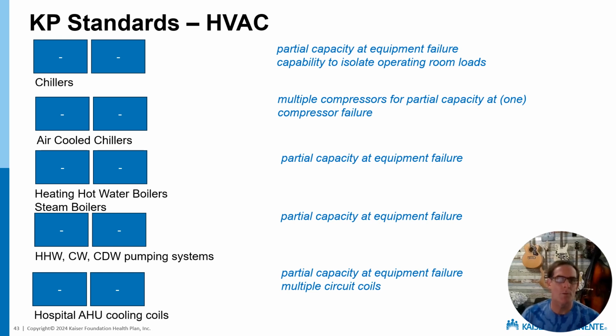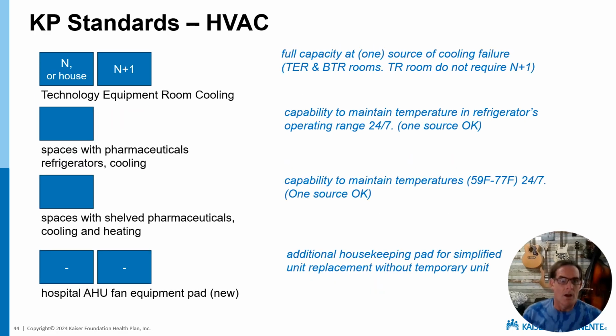We do have a requirement that chilled water capacity should be able to isolate over to the operating rooms. And we have another line in our standard for multiple circuit air handling coils. Larger technology rooms are N+1. Smaller technology rooms are not. And then we get to pharmaceuticals.